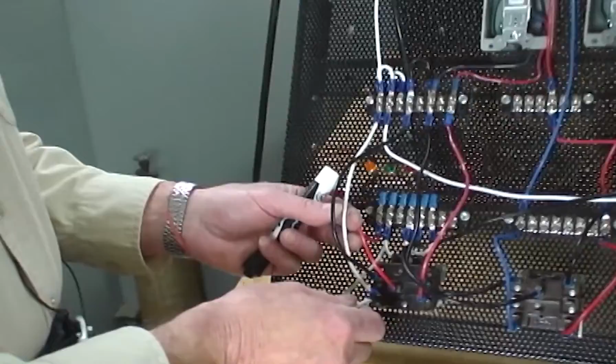Let's chase out this relay 1 coil. Remember, I had neutral plugged in here, so I got one side of the relay 1 coil done right there. Let's finish chasing it out to see where it goes. The other side of the coil is this right here. We've got this red wire that comes up, goes through this terminal strip, comes around, and oh, go figure, goes right in here to one side of a switch.